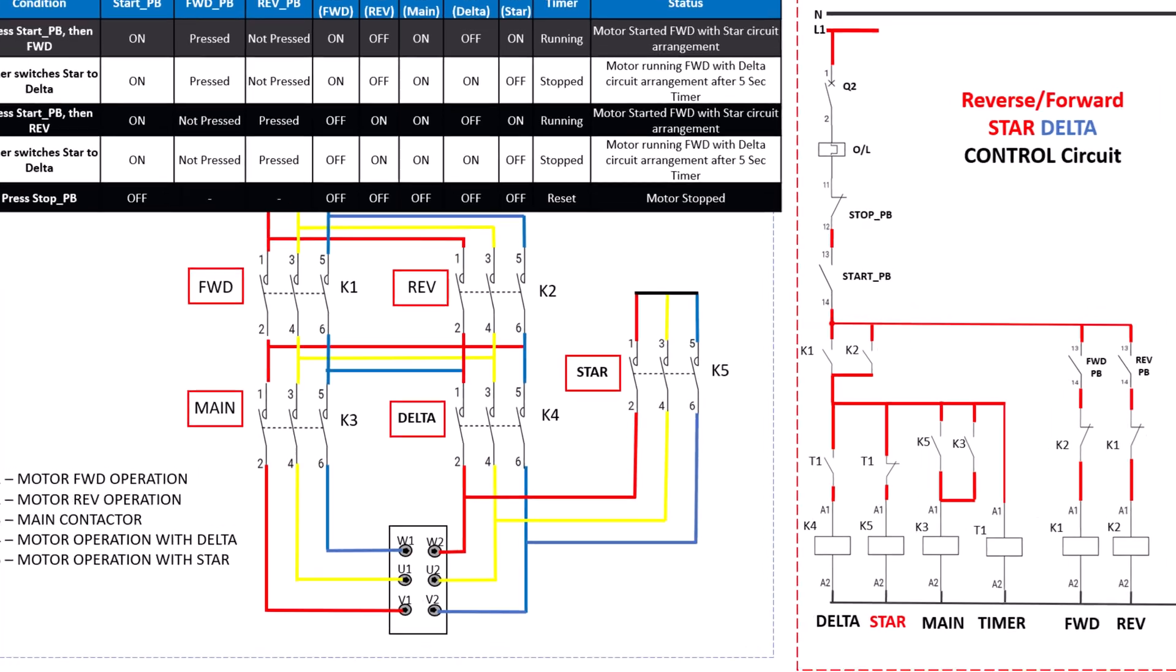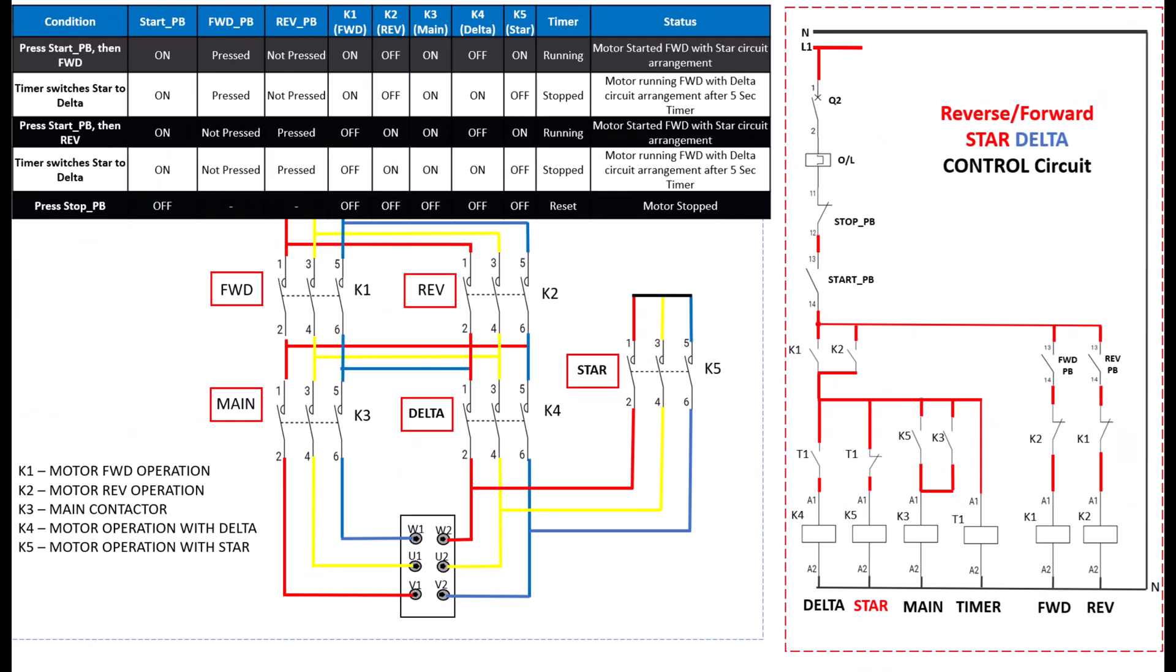To reverse the motor's rotation, we have to swap two phases, such as the red and blue phases, which alters the direction of the rotating magnetic field and changes the motor's direction. So, don't get confused about how the motor will start in reverse direction with K2 reverse contactor. It is because when you swap any two phases, the motor direction changes as the direction of the rotating magnetic field changes.